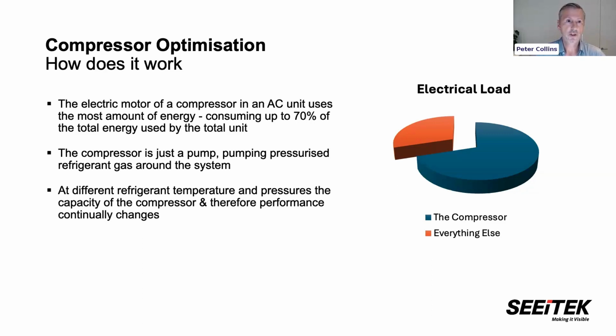Essentially, in the last 50 years a heat pump or air conditioning system hasn't changed much - it's a box with heat exchange coils and fans that pumps gas around the system. The refrigerant, or gas within the system, is continually changing depending on the conditions it's operating with - changing temperatures, changing pressures. So the impact is you're having a dynamic impact within your air conditioning system or heat pump. In other words, if you've got a high load - the swimming pool or aquatic centre is full - there's going to be high demand on the system. If it's empty, there's not going to be such a high demand.